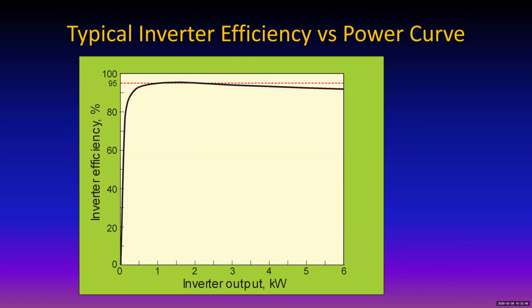Now, this also applies to battery storage, because the battery storage, of course, is DC, and the battery has to have an inverter in order to tie in and provide AC. So this whole matter of milliseconds to connect applies to batteries as well, because they connect to the grid by way of an electronic inverter. So batteries can be very helpful if you want to keep the grid stable, because they can connect and deliver whatever the grid wants very quickly.